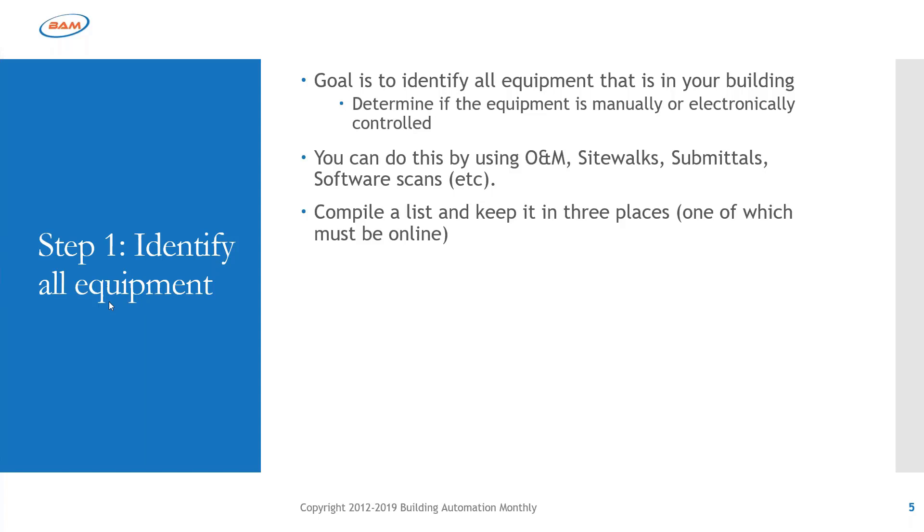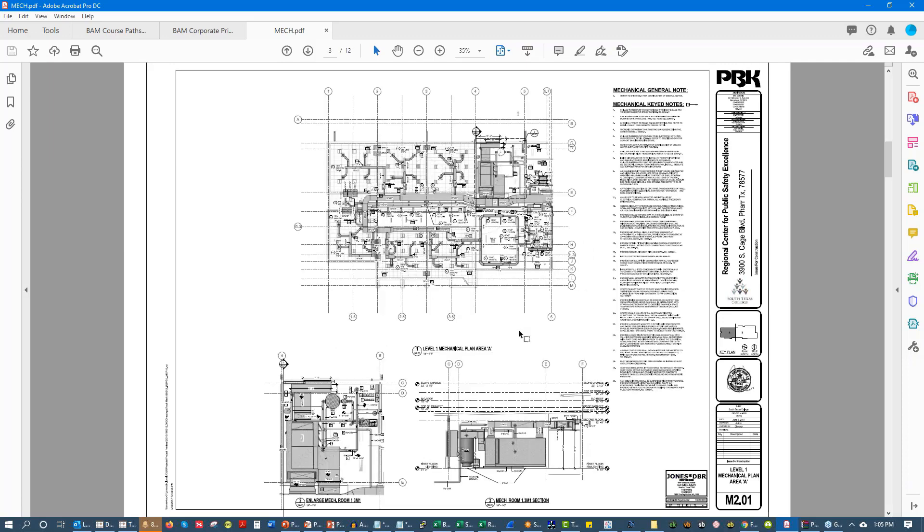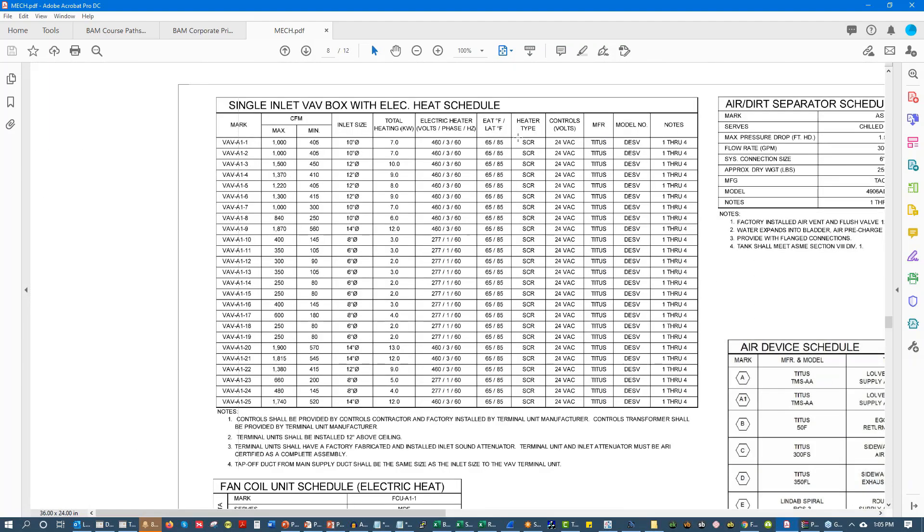I highly recommend finding your control submittals, mechanical drawings, electrical drawings, and O&M manuals — all documentation from previous projects. When I look at my mechanical drawings, the main focal point is the equipment schedule — that's where I start grabbing information. You'll be validating this, maybe using a CMMS, work order management system, or asset management system. A lot of buildings don't have those, so we'll start to build a database — something as simple as an Excel sheet with system, building, floor, whatever taxonomy you want.